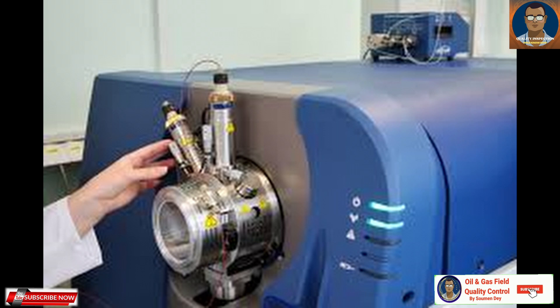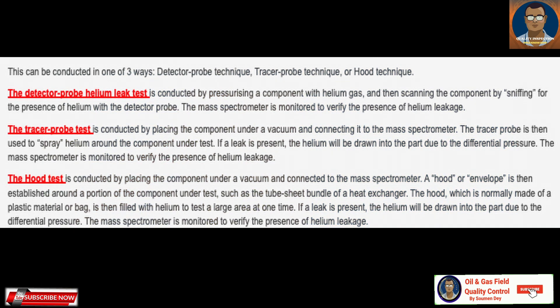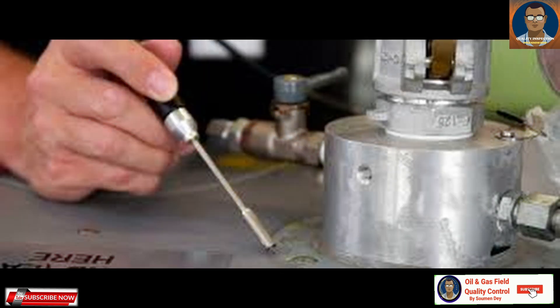This can be conducted in one of three ways: the detector probe technique, the tracer probe technique, or the hood technique. The detector probe helium leak test is conducted by pressurizing a component with helium gas and then scanning the component by sniffing for the presence of helium with the detector probe. The mass spectrometer is monitored to verify the presence of helium gas.